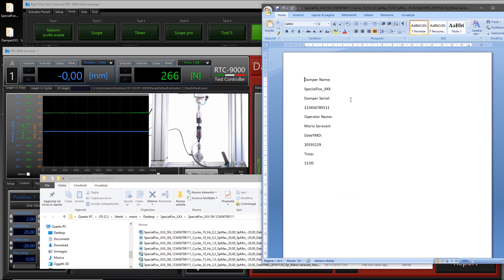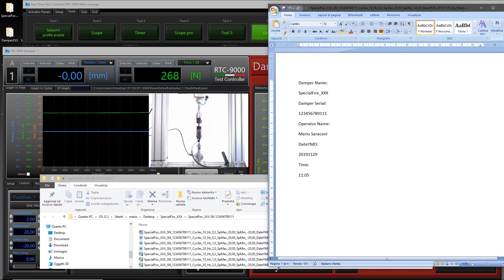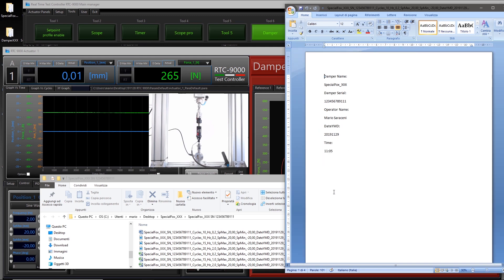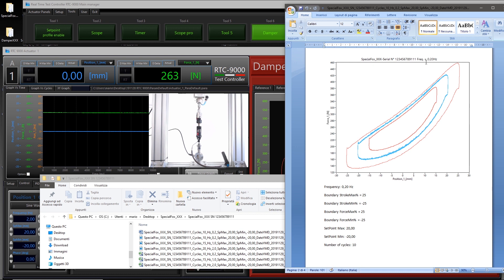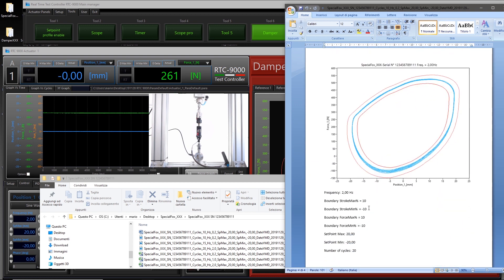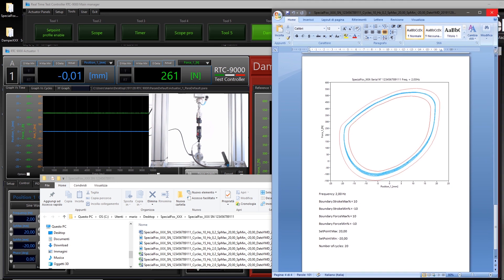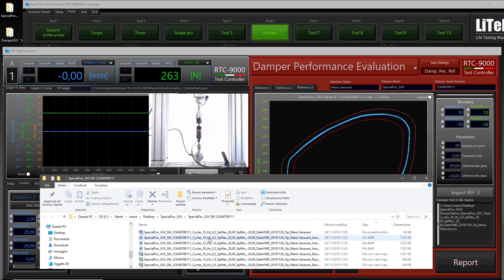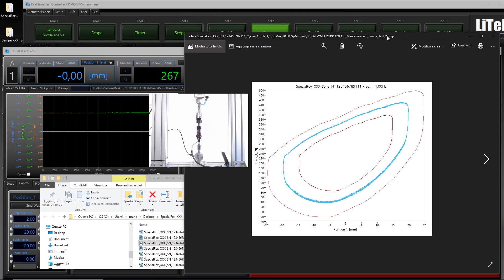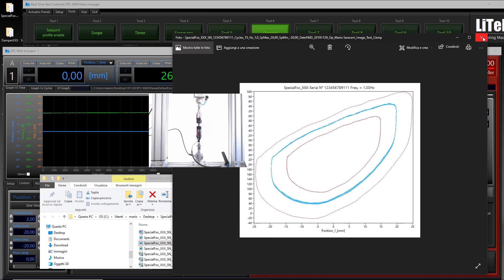Let's see what is on the first page of the report: the damper type, the serial number of the damper tested, the operator, the date, and the time. Then we have the first image with the boundary and the test settings, the second image, and the third image. Let's close this file.